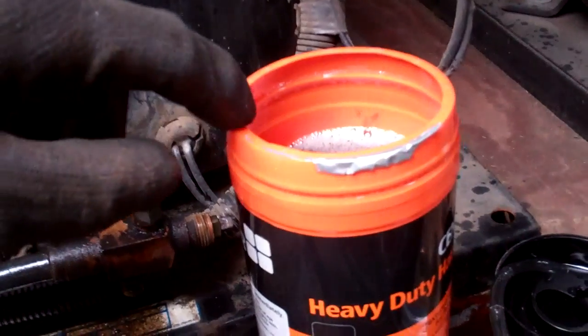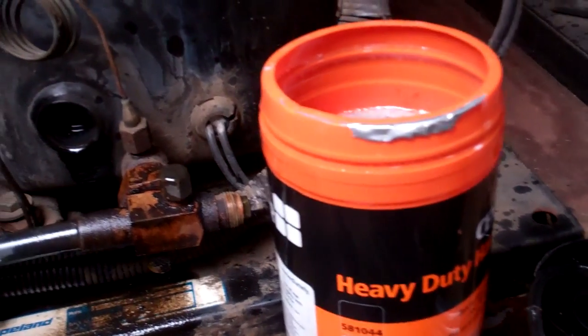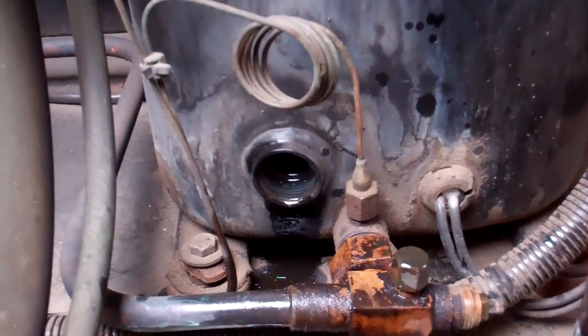I've just been putting the oil in here for now and I want to see what sort of volume we've took out, because the system's been running low on oil due to a leak in the evaporator. I reckon we've took nearly a litre out so far.